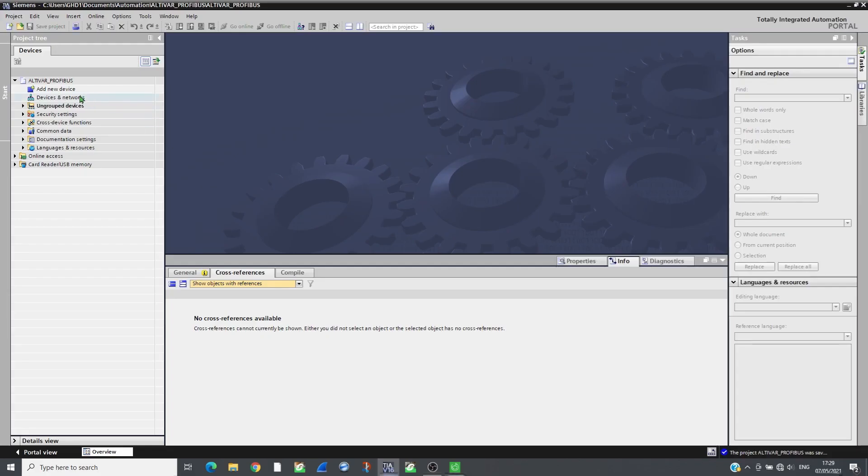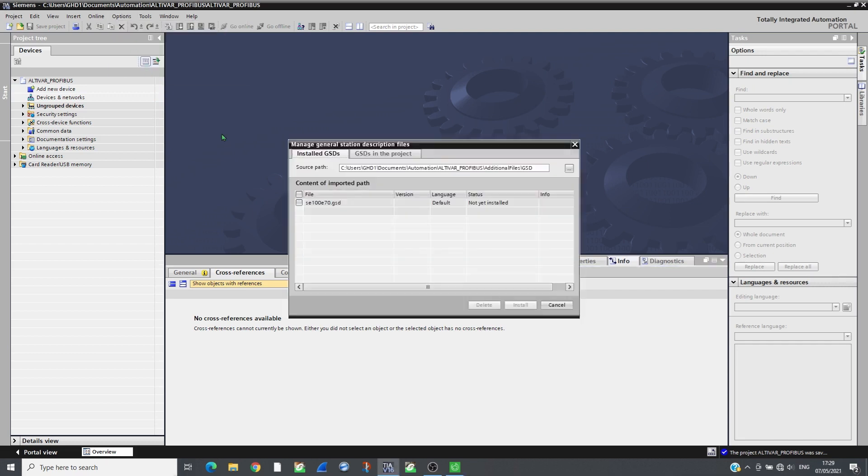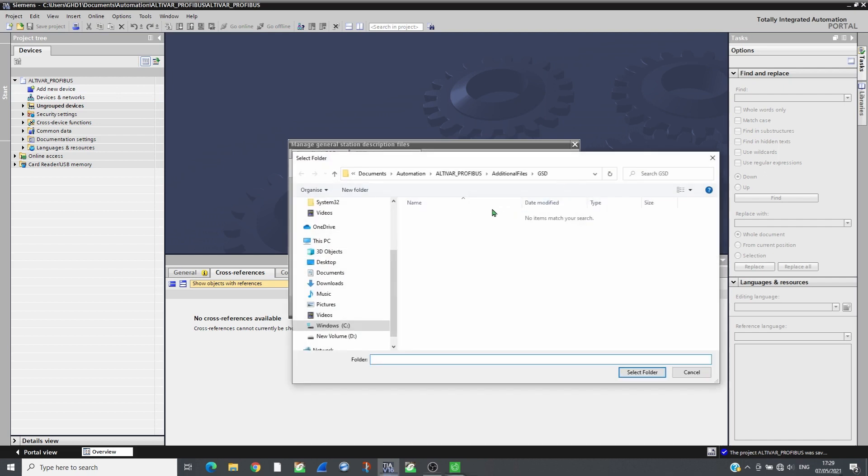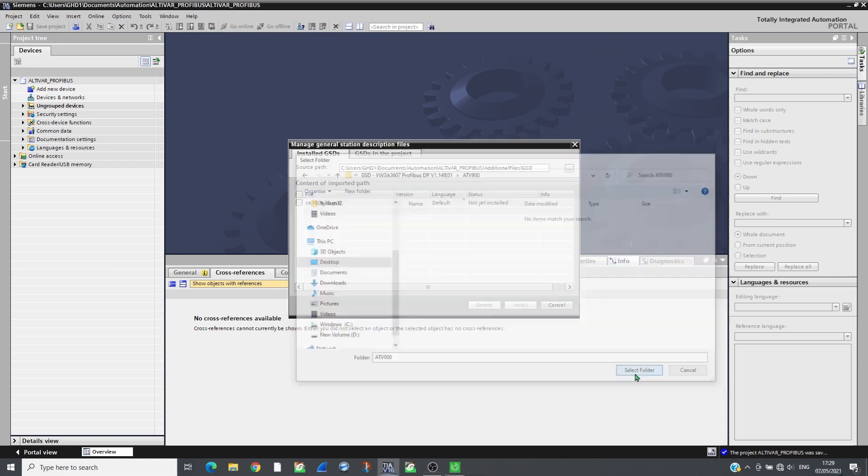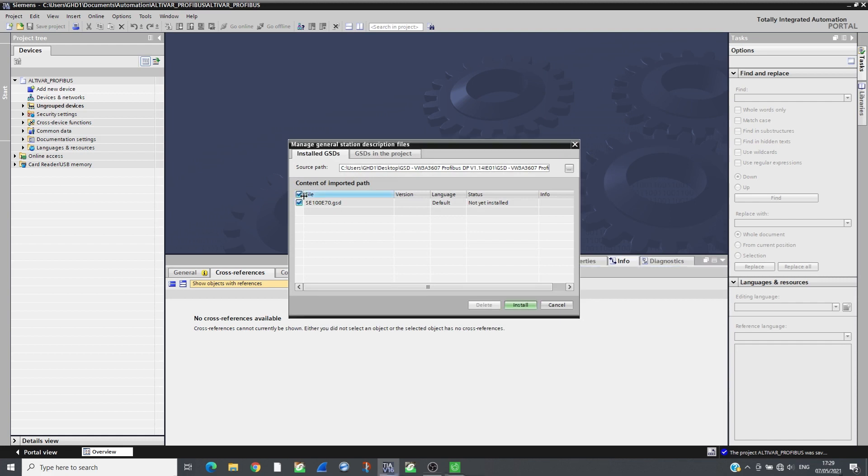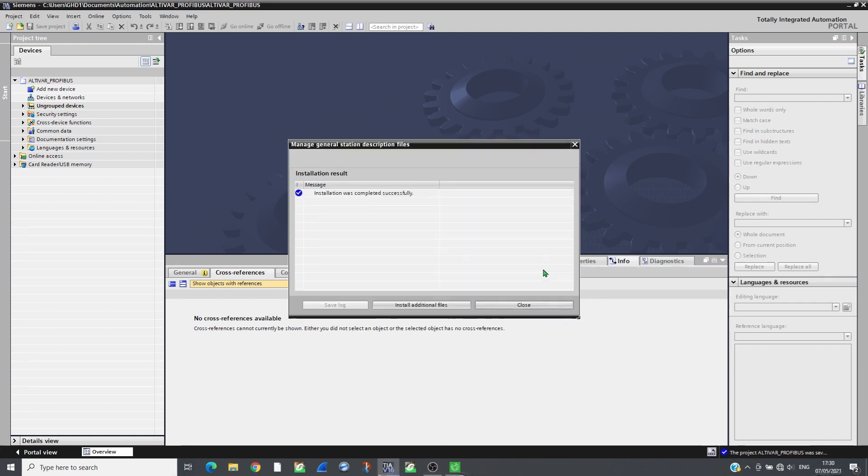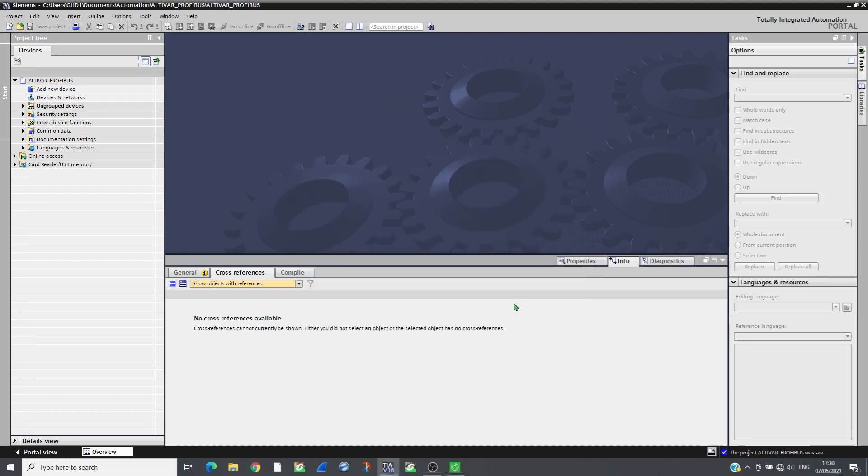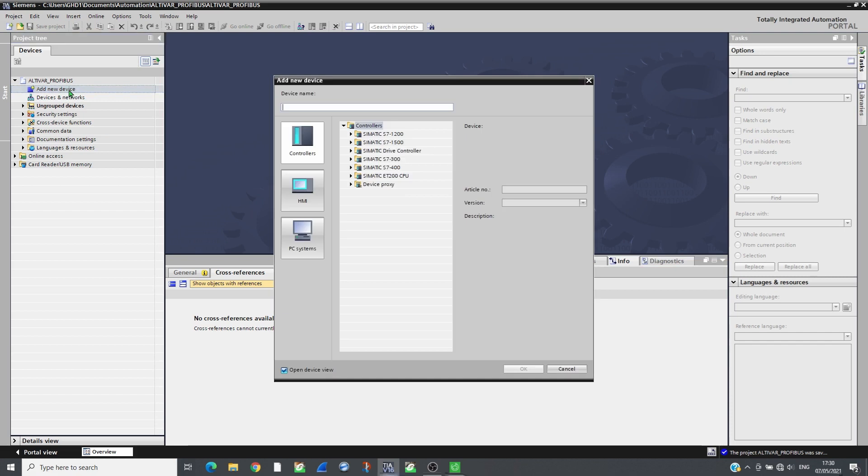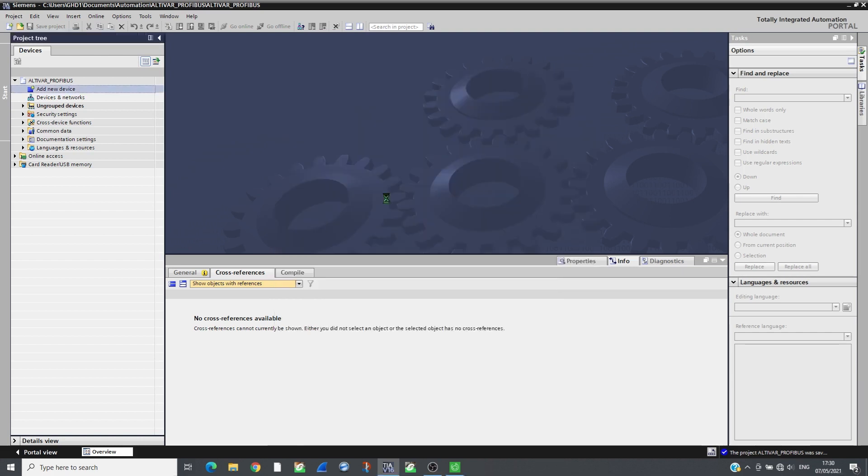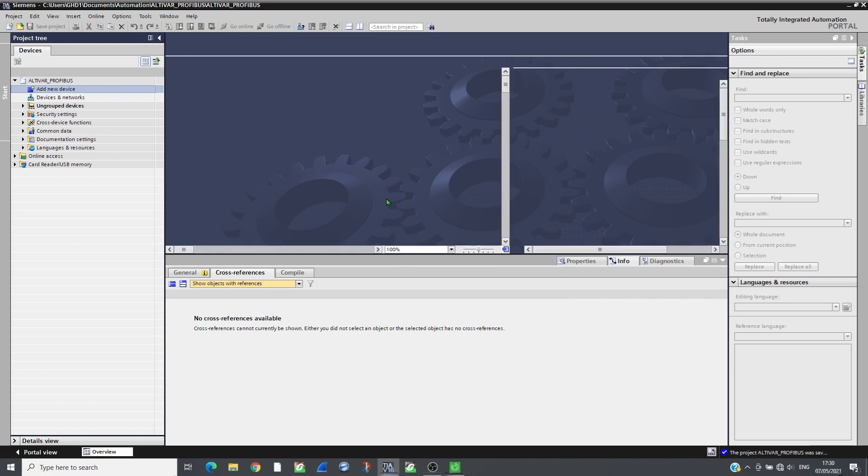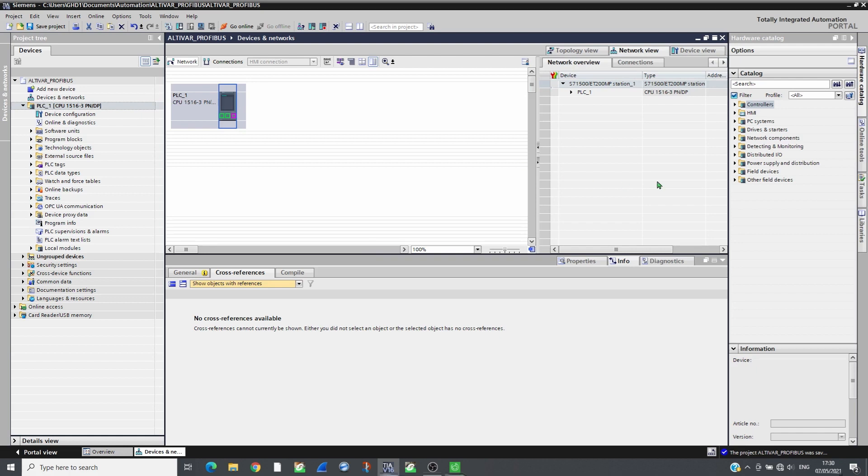Create a new project on TIA Portal and import the GSD files that can be downloaded from Schneider website. Add the CPU. In the network view, add an ATV930 from the catalog and assign it to the PLC PROFIBUS interface.